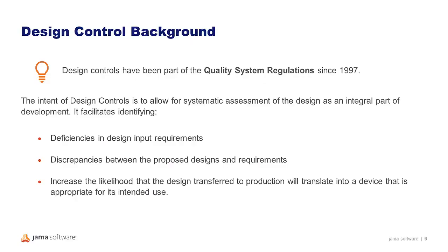So let's start with design control background. So design controls have been part of the FDA QSR since 1997. So it's been a long time. The FDA initially implemented design controls to try to help medical device manufacturers identify deficiencies with design input requirements, to identify discrepancies between proposed designs and requirements, and to increase the likelihood that the design transferred to production is going to translate into a device that is appropriate for the intended use and satisfies the user needs.